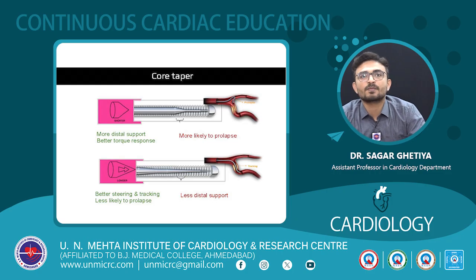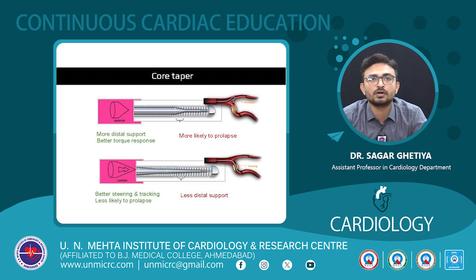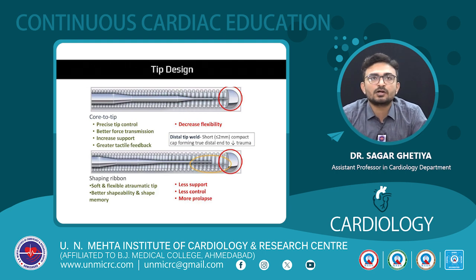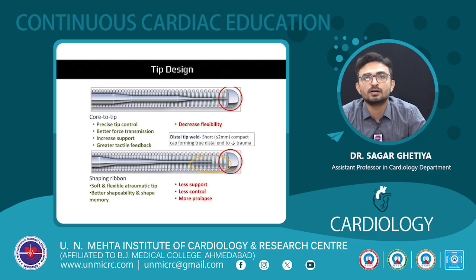While a longer taper results in better steering and tracking and is less likely to prolapse, there will be less distal support. So, tip design. There are two kinds of tip design. One is core to tip and another is shaping ribbon. In the core to tip design, the core reaches up to the end of the wire, while in the shaping ribbon design, the core terminates early and the distal most part is formed by a flexible metal strip, which is referred to as the ribbon. So what are the advantages of the core to tip design?